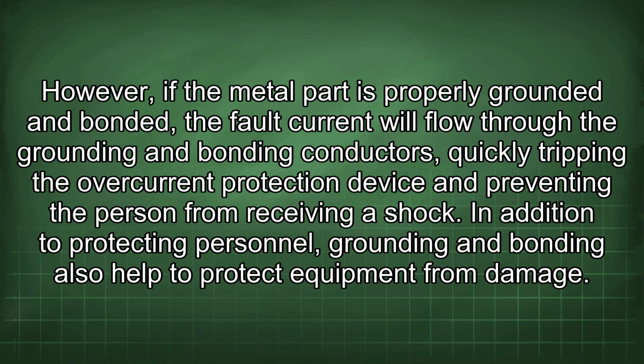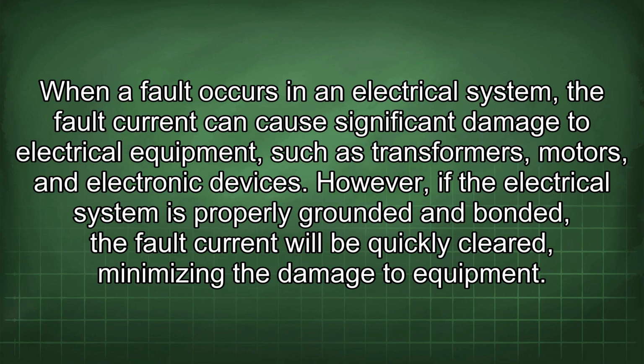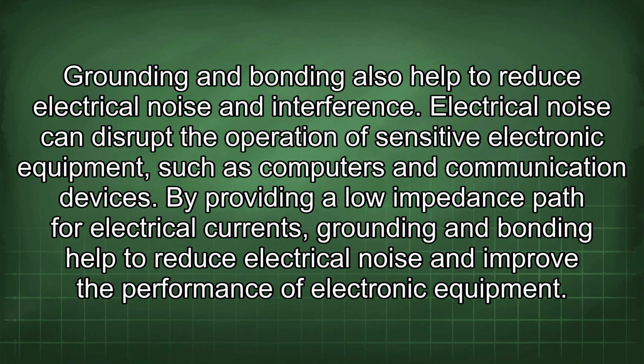In addition to protecting personnel, grounding and bonding also help to protect equipment from damage. When a fault occurs in an electrical system, the fault current can cause significant damage to electrical equipment, such as transformers, motors, and electronic devices. However, if the electrical system is properly grounded and bonded, the fault current will be quickly cleared, minimizing the damage to equipment. Grounding and bonding also help to reduce electrical noise and interference.